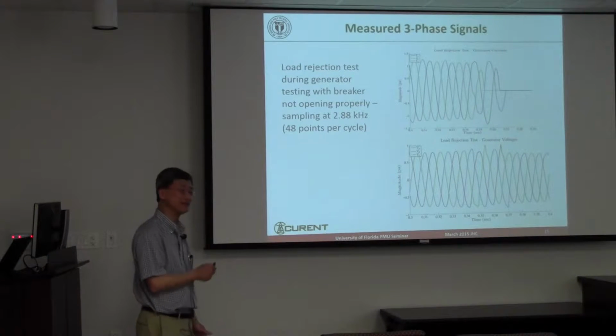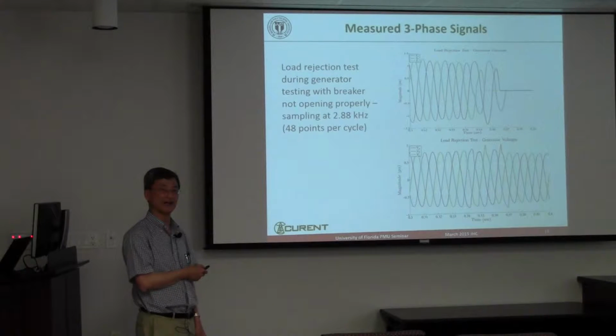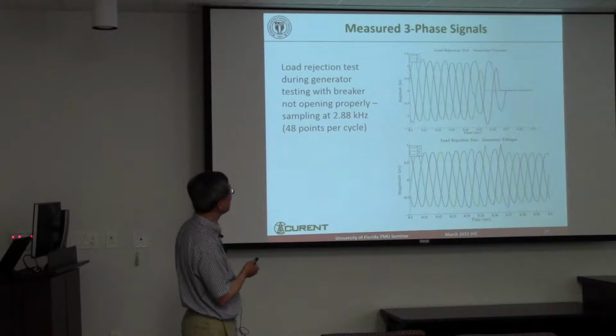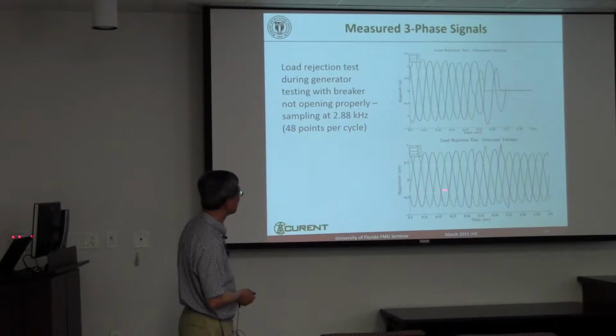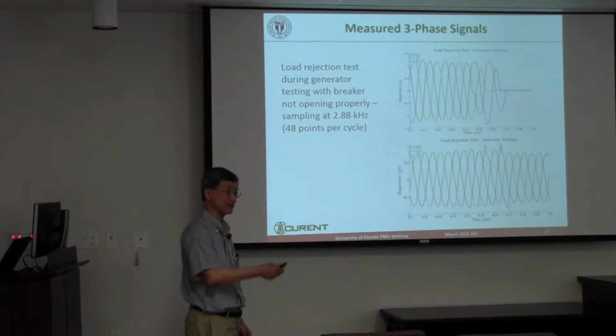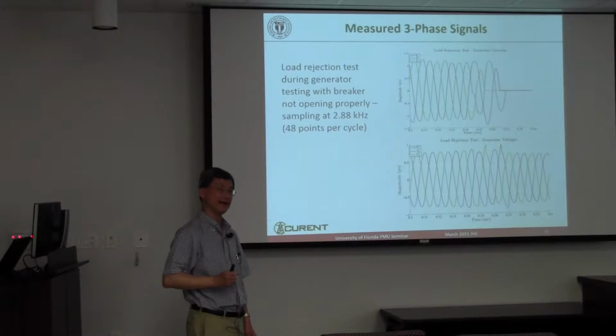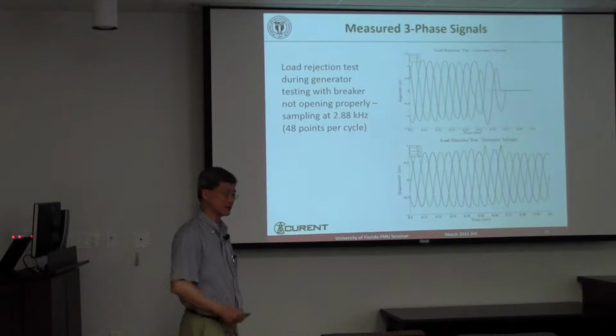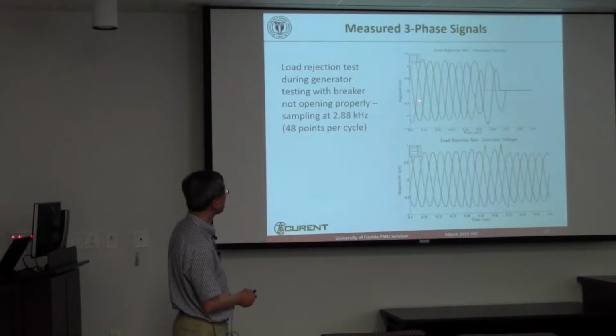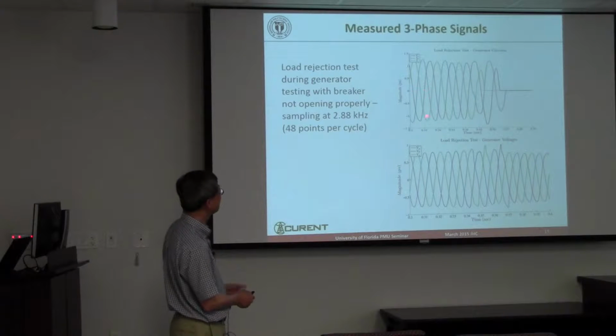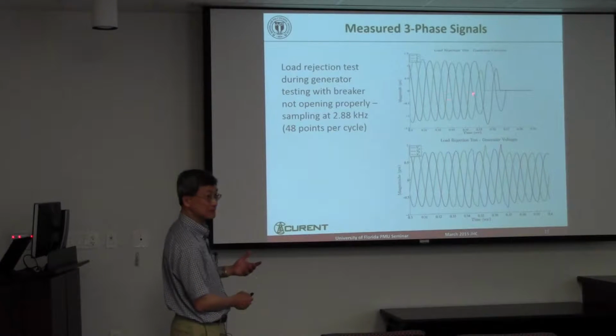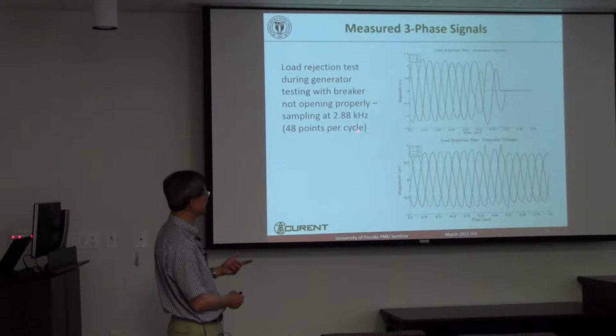So why can you not compute phasors instantaneously? Here is the actual measurement of three-phase current and voltage during a generator load rejection test — basically you open the circuit breaker and then do the calculations. This is a hydro unit, and you can see the current is sinusoidal enough, but not perfectly sinusoidal, and the amplitudes in the different phases are not the same. The voltage is similar. There are 48 points per cycle, since this PMU samples at 2.88 kilohertz.